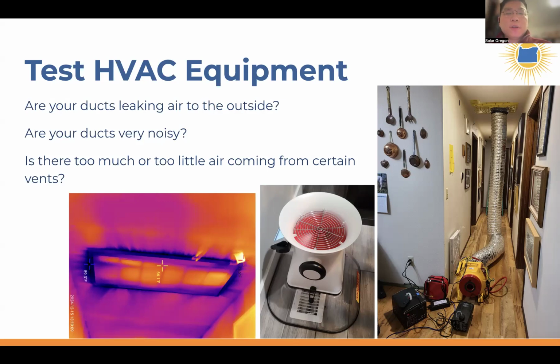So there are some things to do to test HVAC equipment. One is we want to see that the amount of airflow to each room is roughly what it should be. If you have a giant room and you have 20 CFM of air going through that supply grill, then that's not even close to being correct. Same thing, we want to know how much leakage there is in ducts, especially ducts going outside of conditioned space, because you're literally throwing money out the roof or out of your crawl space if you have duct leakage.